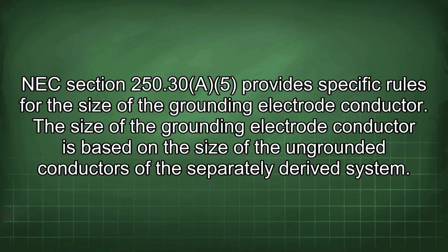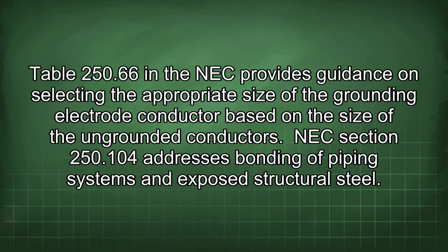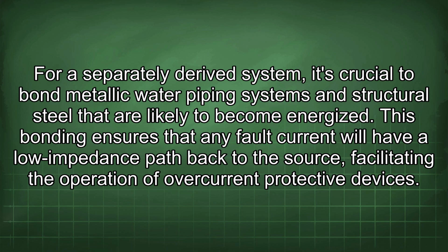NEC Section 250.30 provides specific rules for the size of the grounding electrode conductor. The size of the grounding electrode conductor is based on the size of the ungrounded conductors of the separately derived system. Table 250.66 in the NEC provides guidance on selecting the appropriate size of the grounding electrode conductor based on the size of the ungrounded conductors. NEC Section 250.104 addresses bonding of piping systems and exposed structural steel. For a separately derived system, it's crucial to bond metallic water piping systems and structural steel that are likely to become energized. This bonding ensures that any fault current will have a low impedance path back to the source, facilitating the operation of overcurrent protective devices.